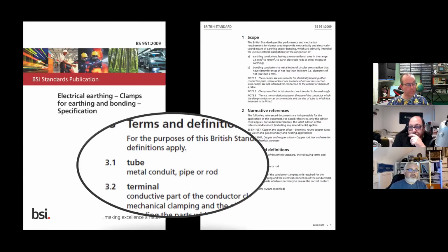They'll say, nope, BS 951's not allowed on a cable. Absolutely, but it was. And you, the network, use that to connect my electrical installation to the general mass of earth via an older type. So you have to maintain that. Now, if it's not safe, you need to find alternative means, which can be used via these spring clips or digging up the ground outside, isolating the cable, connecting in the head, etc., etc. There are other means we have to take.